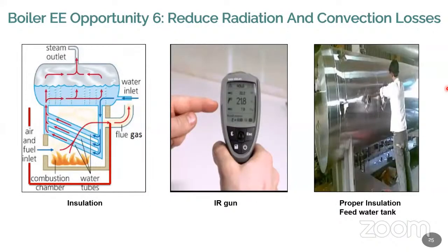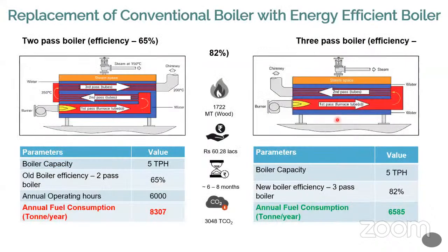Then the losses: you have to enclose it almost completely, with an aluminum cladding. Apart from that, inside the boiler you can have ceramic bricks. When the insulation fails, then automatically the heat will come out, so that is a huge loss. So remember that insulation should be very proper, so that you always measure the temperature all around the system, not only the boiler but all the auxiliaries also, to ensure the insulation. Okay, so this is the conventional system. This is the 2 pass boiler.